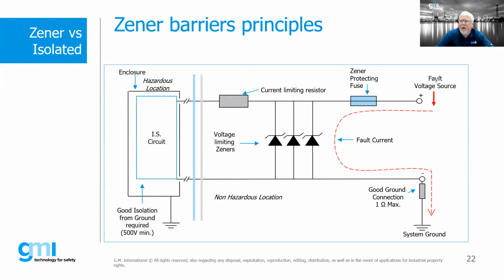So if we had a fault condition, as we have an increase of energy, we hit our current limiting resistor. As the voltage increases, the Zener diodes will open up. These diodes are rated, say, at 28, 29, or 30 volts, whatever the maximum is. Once it starts hitting that level, the excess voltage is driven to ground. At some point, if left unchecked, the current limiting resistor could blow, or the fuse could blow.